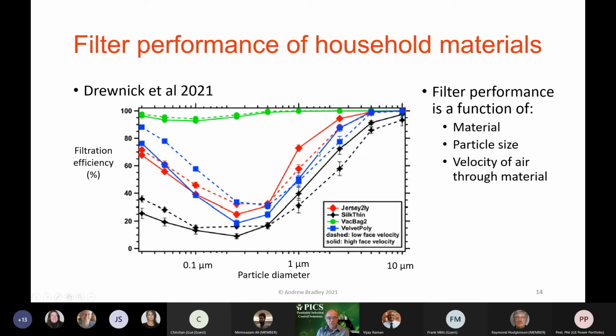The other thing to note is filtration is also a function of the velocity through the material. The solid line represents high velocity and the dashed line a lower velocity. That typically swaps over in terms of effectiveness - at lower velocities they're more effective at filtering smaller particles, but for bigger particles it's the other way around, because of the different mechanisms preventing filtration.